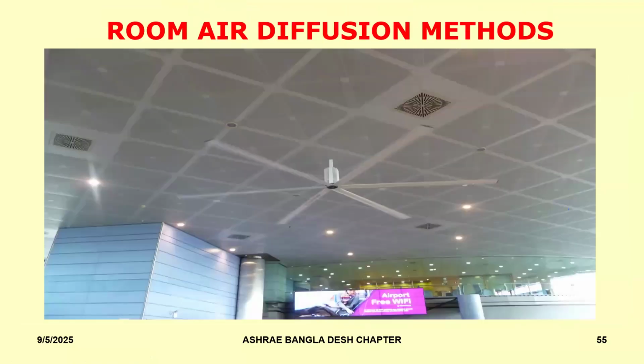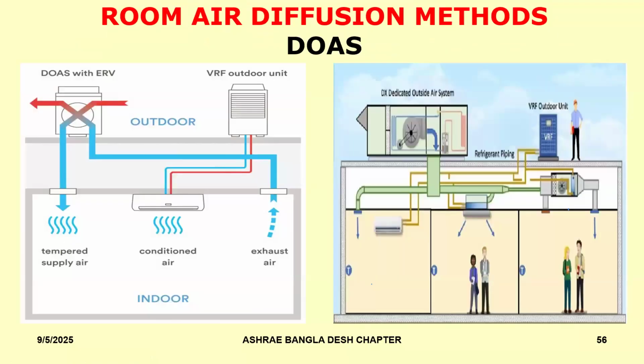Now, one of the best ways of trying to make sure that you get the right amount of outside air delivered into the space is by trying to decouple the load inside the space. All of you are familiar with load evaluations. When we do load evaluations, we have a sensible component of the load and a latent component of the load. Now, a large part of the latent component of the load comes from the occupancy of the people inside, unless, of course, you have certain processes. But by and large, in commercial occupied spaces, a large part of the latent load comes from the outside air and also from the occupants.